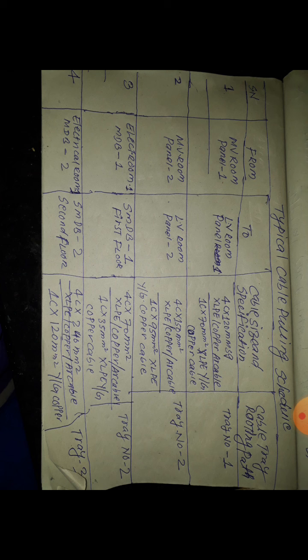So for 4 core 150, half the value is 75, and since we have 95, we can use 1 core 95 mm square XLPE YG yellow green. So the earthing cable has a yellow and green color code. It is single core, and copper cable is used. Another, third number, is electrical room 1 to MDB1.